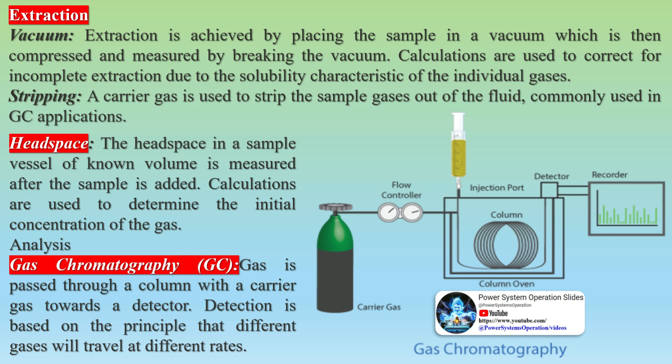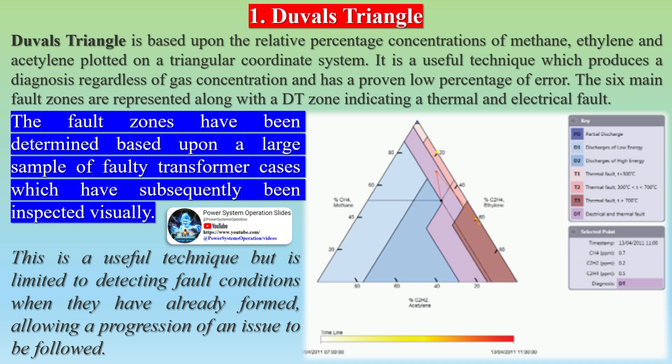For analysis, Gas Chromatography (GC) passes gas through a column with a carrier gas towards a detector; detection is based on the principle that different gases travel at different rates. Photoacoustic Spectroscopy (PAS) exposes gas to infrared (IR) energy passed through a selected filter; the absorbed IR energy is converted to sound, recorded via a microphone, based on the principle that different gases absorb different filtered energies. The resulting signature profiles from both methods identify specific gases and their concentrations in the insulation fluid.